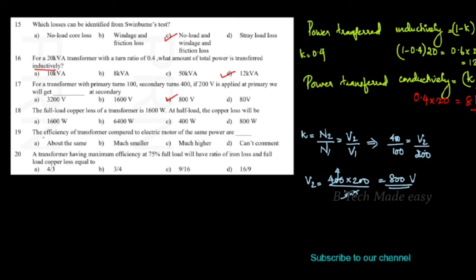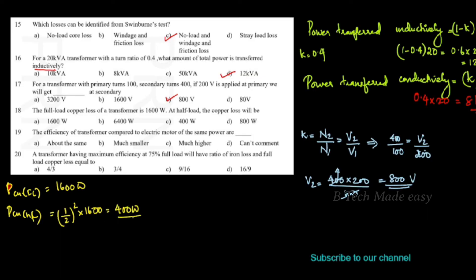The full load copper loss of a transformer is 1600 watts. At half load, the copper loss will be: half load copper loss equals (1/2)² × 1600, which is 1/4 × 1600 = 400 watts. So the half load copper loss is 400 watts.